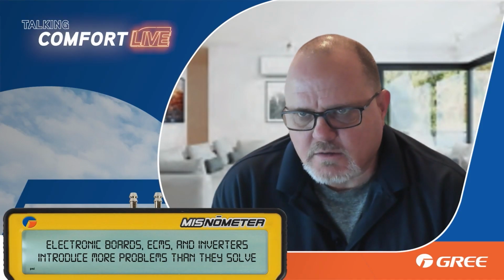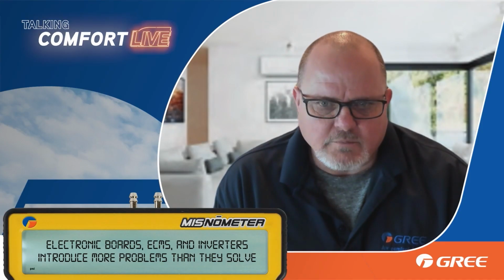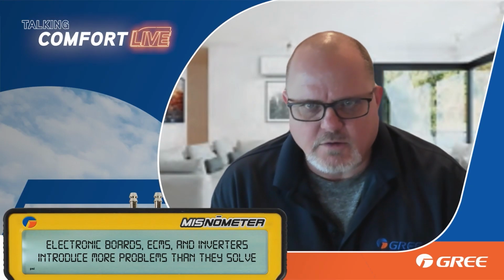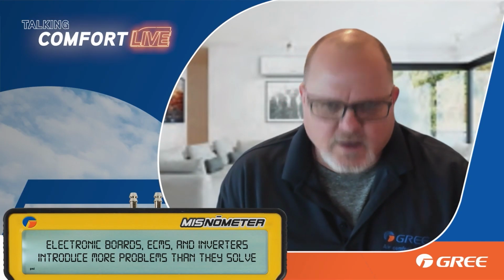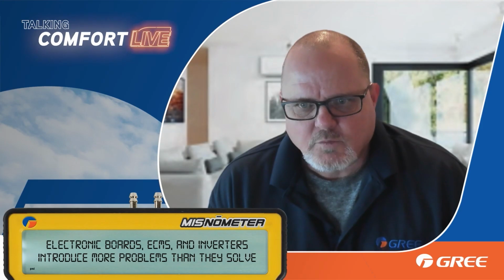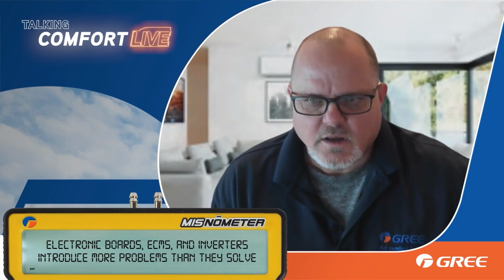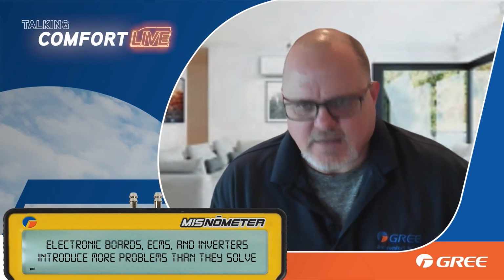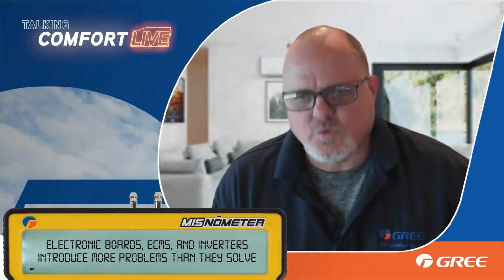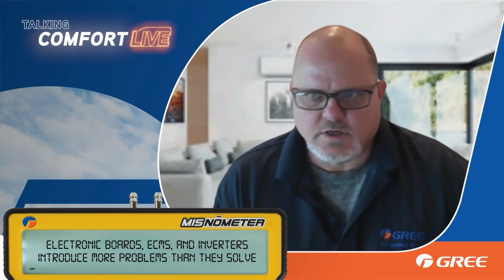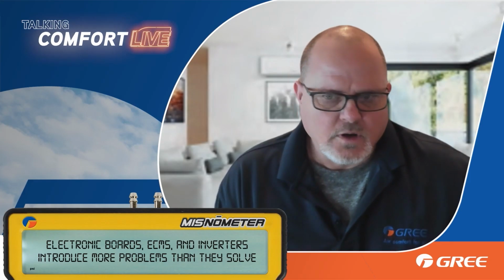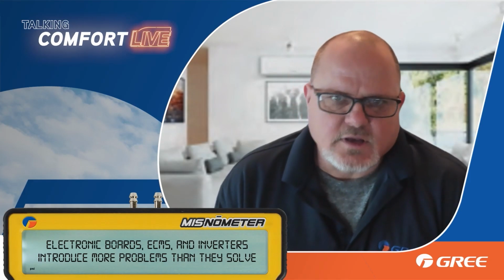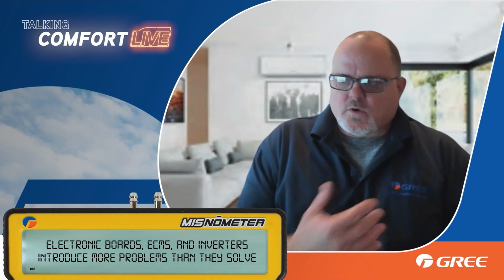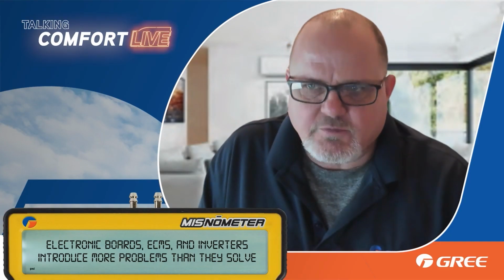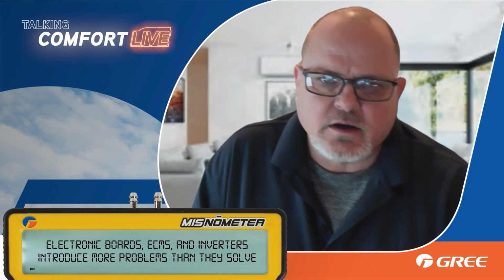Some people look at it as a negative that a machine has so many different error codes. But on the positive side, it has so many different error codes. Rather than the machine actually getting damaged, the compressor getting damaged, or like you were talking about, James, where the unit's freezing up, or a lot of these other things that can happen to these machines, we're improving that technology and keeping that from happening and having the machine go out on an error code.